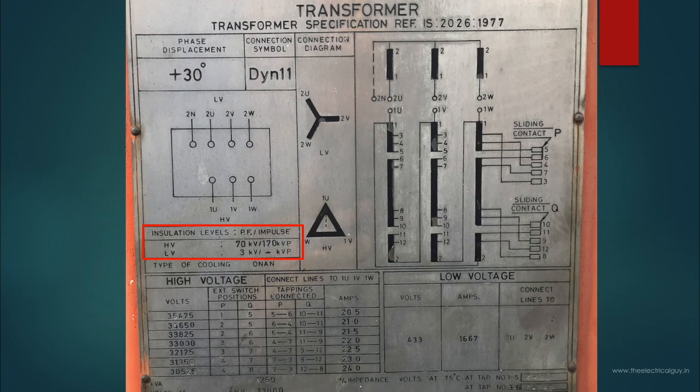Moving on here you can see the insulation levels. This is power frequency voltage and impulse withstand voltage. The first value 70kV and 3kV indicates the power frequency voltage for high voltage winding and low voltage winding respectively. Similarly the 170kV peak indicates the lightning impulse voltage for high voltage winding. For LV winding it is not applicable.